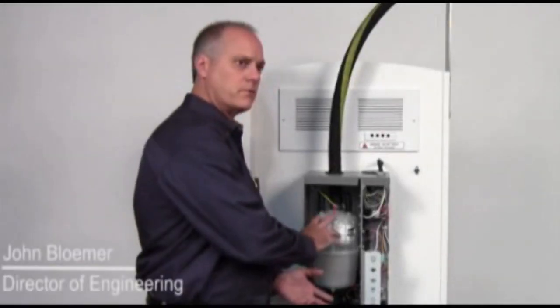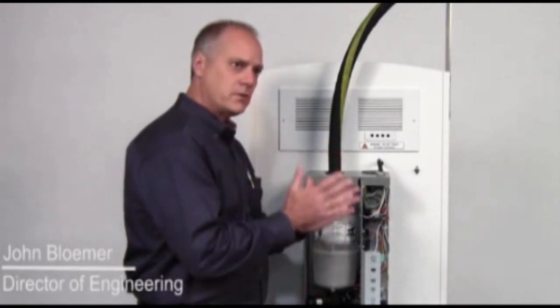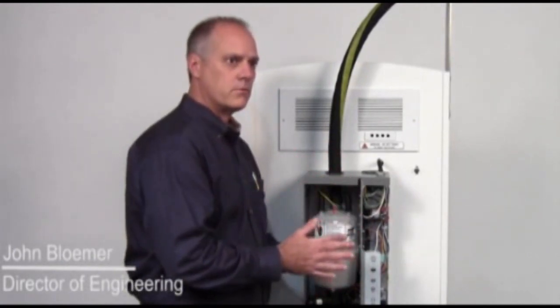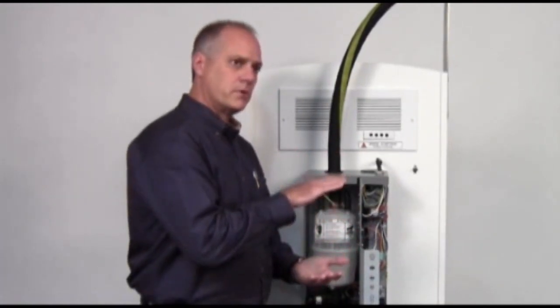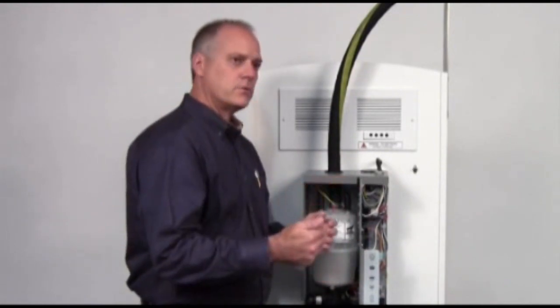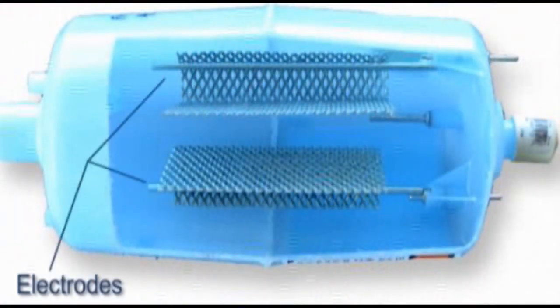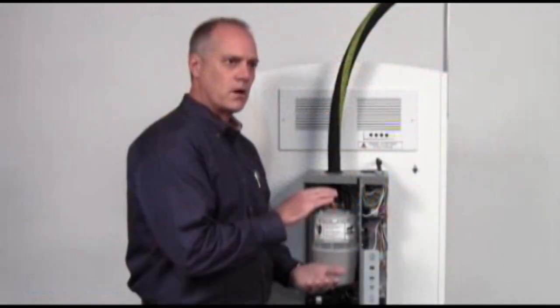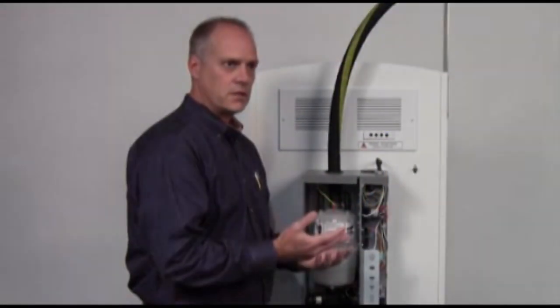The canister itself is very simple. It's got basically two electrodes that go down through the unit. The water fills up into the canister, and the electricity then passes from one electrode to the other. And as electricity is passing between the electrodes, that's what causes the water to boil and create the steam.